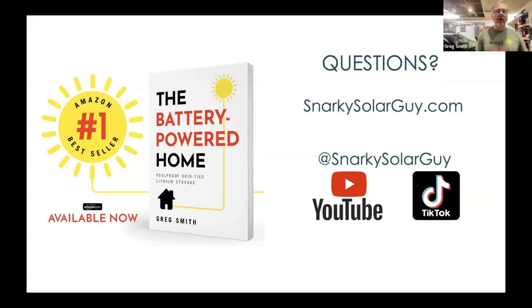Earlier you referred to a system that took 30 seconds to switch over. Was that a specific transfer switch? Yeah, I get that reaction, you don't want to use that one. Luckily, that's an older system. 30 seconds is absurdly long, and that company has reduced it down to 2 seconds, which seems to be standard for most energy storage systems now. Still, 2 seconds is an extremely long time in electrical terms. It will not keep your computer on, and the lights will flicker. So I recommend putting a small UPS on your computer system. I have one on my desk with my computer plugged into it.